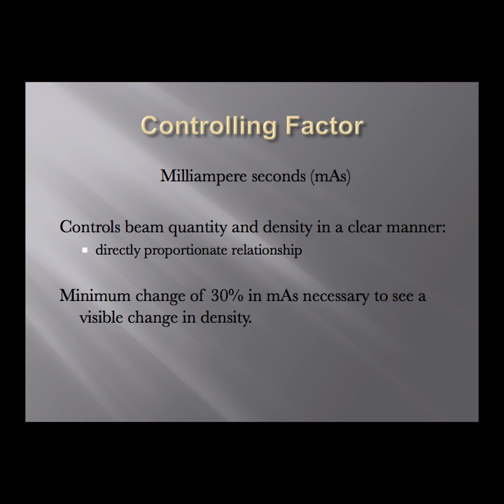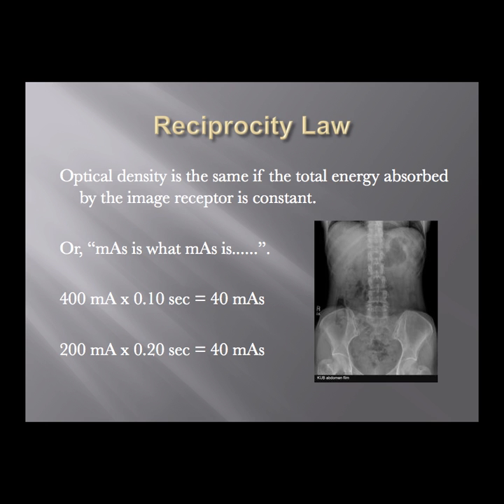So mAs is the controlling factor for density, but to see any visible change at all you need at least a 30% change in mAs — either up or down. If you want to make the film lighter, you need to go down in mAs by at least 30%. If you want to make the film darker to the point where you can actually see a difference, you need to go up at least 30% in mAs.